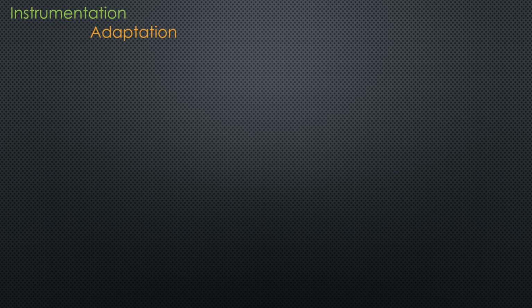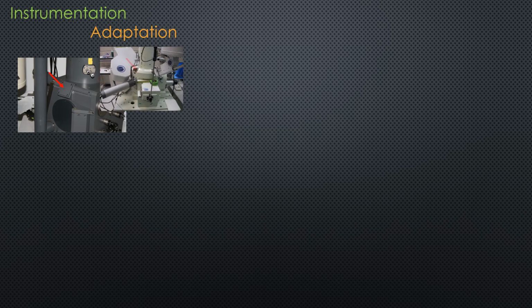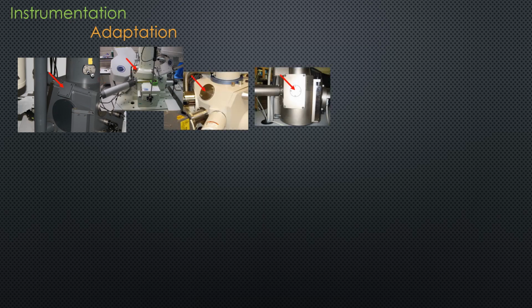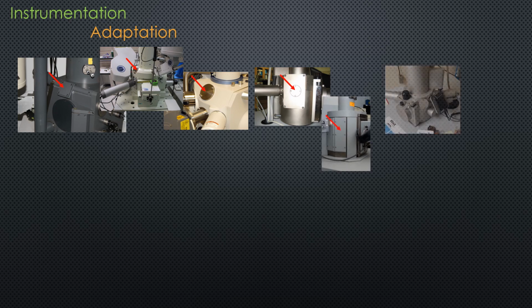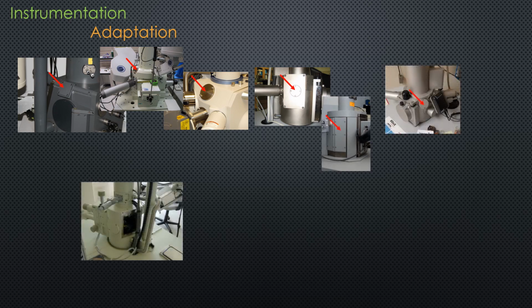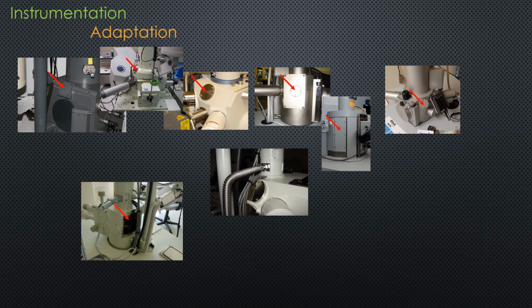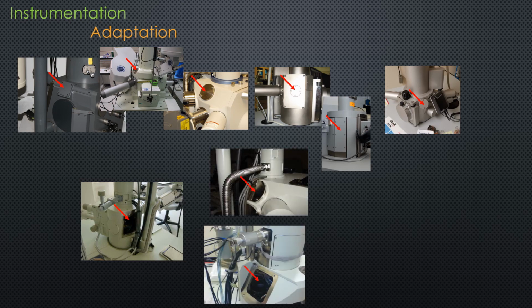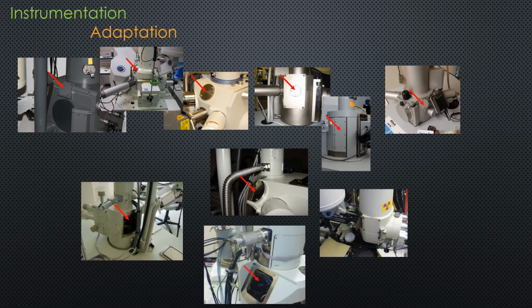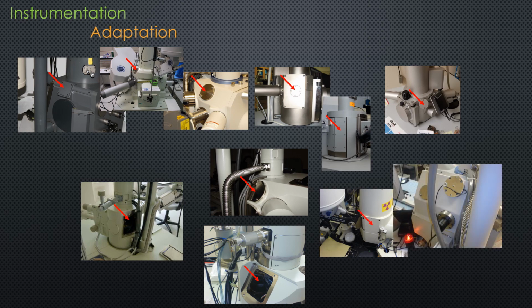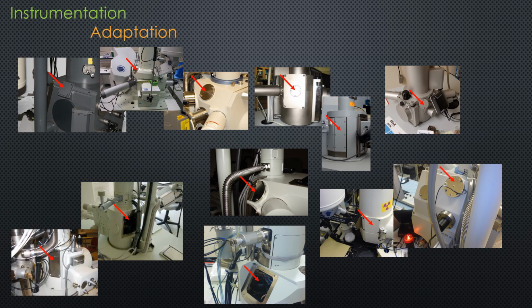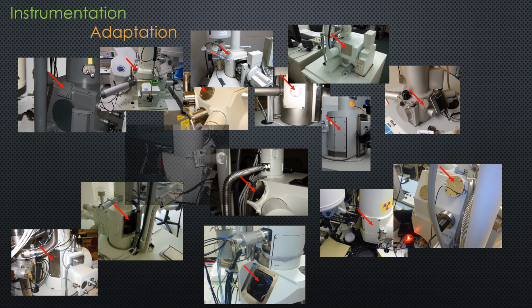To put an X-ray source on your electron microscope, we need a port that will allow us to come in at about 33 degrees. This is typically considered an EDS port or a high angle port. Over time, we won the confidence of all the SEM vendors. Not just anybody can put something on their microscope, which is actually now your microscope. In the past, we've put X-ray sources on JEOL, Hitachi, Zeiss, FEI, and TESCAN.